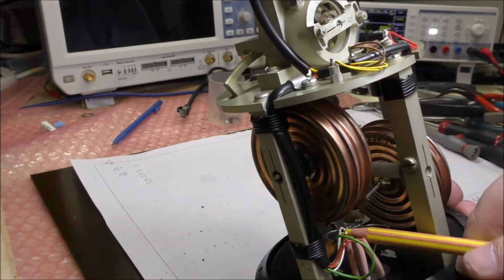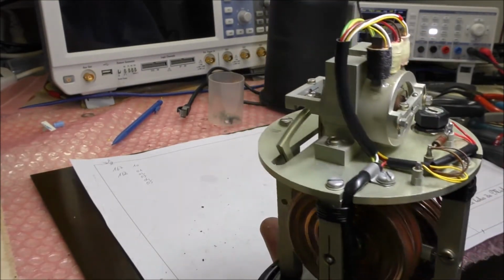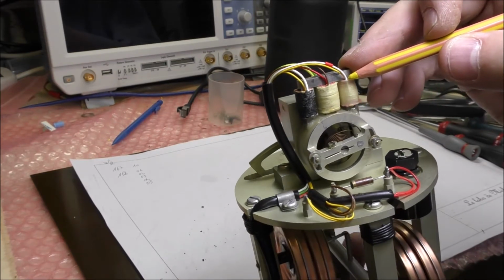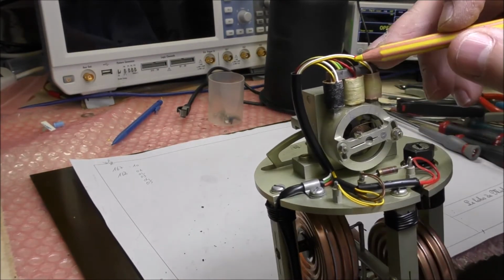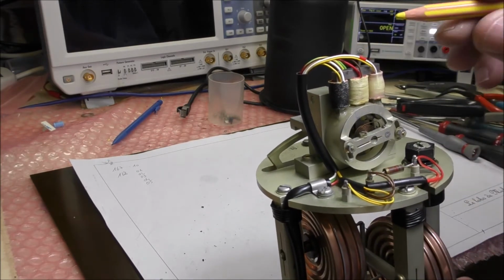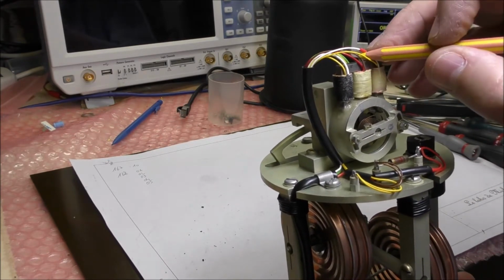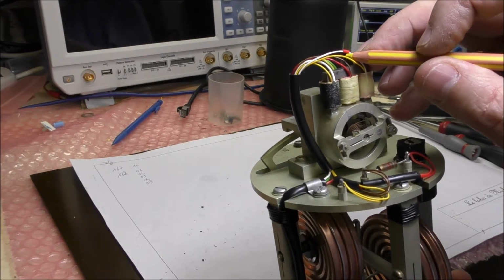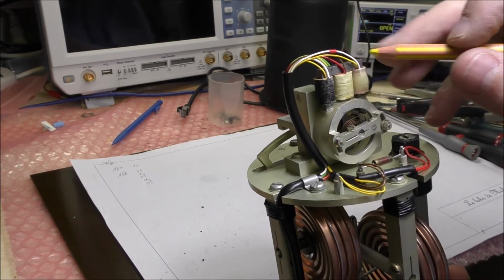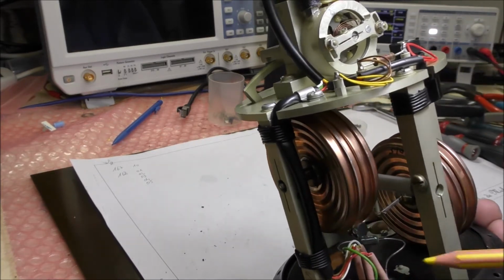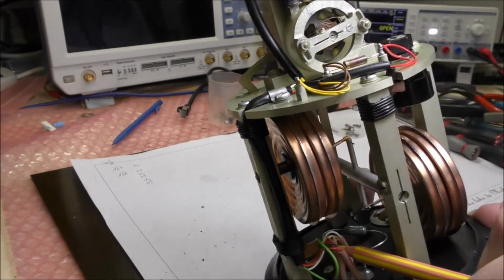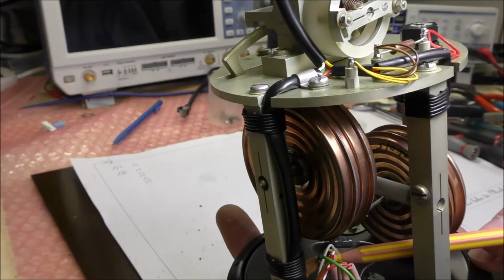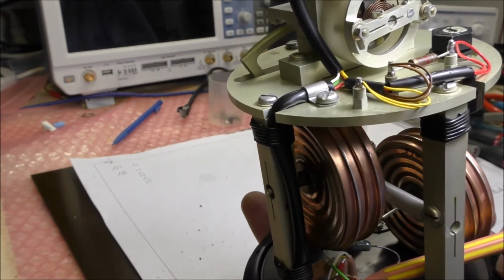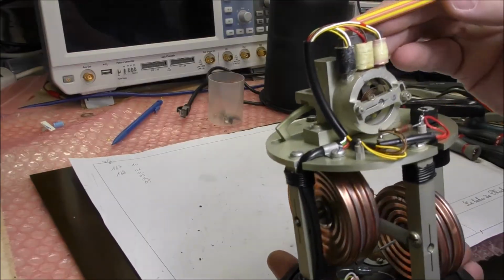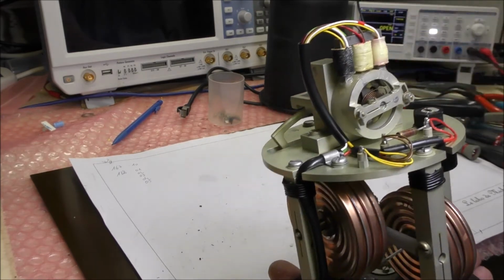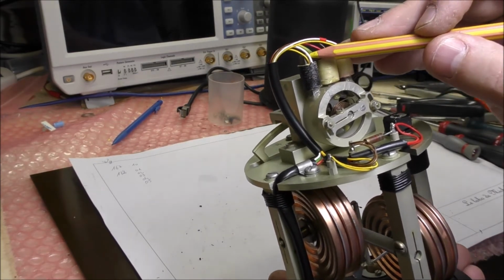And then we have the sensing element. We can see that the 2 coils are connected in series in opposition because these yellow wires are connected together here. So we have only these 2 white wires, one coded with this red tube here, and they are connected here to 2 terminals. We can see that one is in common. So the yellow wire of the excitation is common to one terminal, and this is normal. It is a ground.